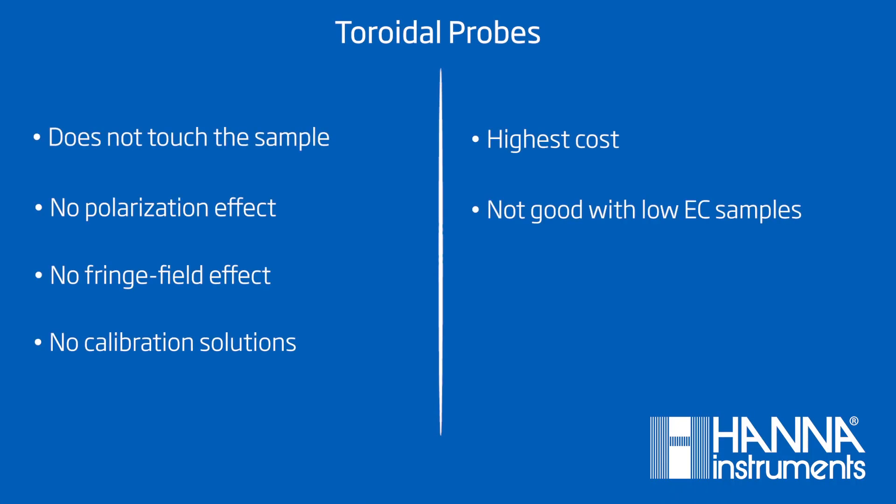Toroidal probes are great because the probe never actually touches the sample, since they are encased in plastic. You don't have to worry about the polarization effect or the fringe field effect. The probe has a very low chance of fouling or getting clogged, and you do not need calibration solutions. They are very accurate in high-range samples, up to 2 Siemens per centimeter. The plastic body is chemically resistant. However, toroidal probes are expensive and not suitable for low-range EC samples. Even though the plastic sheath is chemically resistant, it is not impervious. Be careful not to have organic solvents in your sample, or concentrated chlorine. Select plating baths can also cause issues with incompatibility with the plastic.